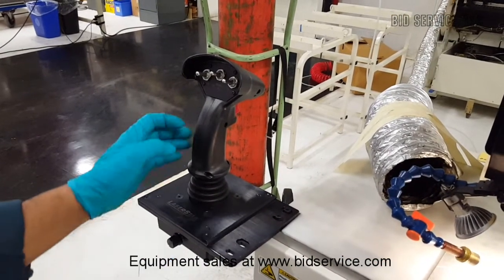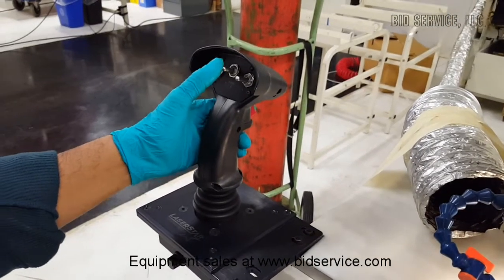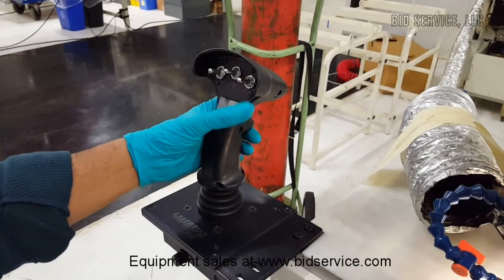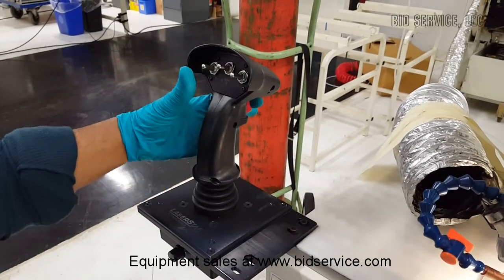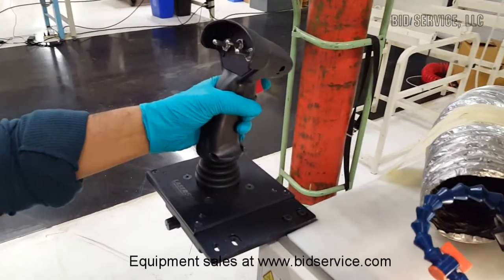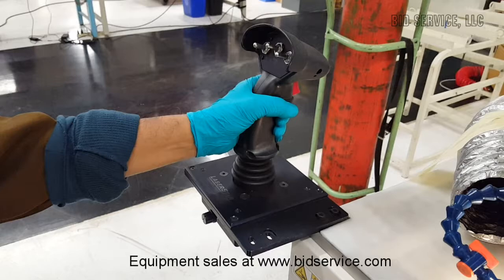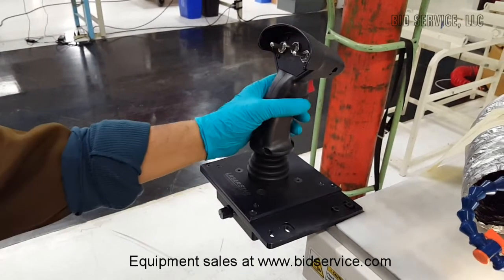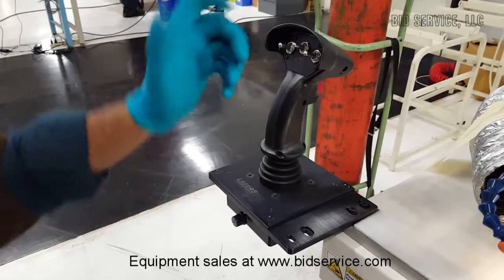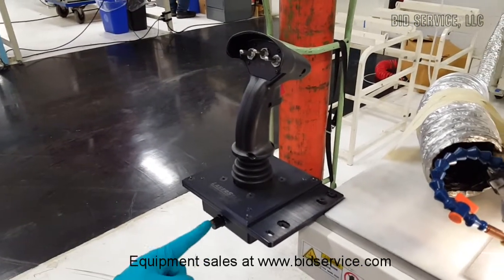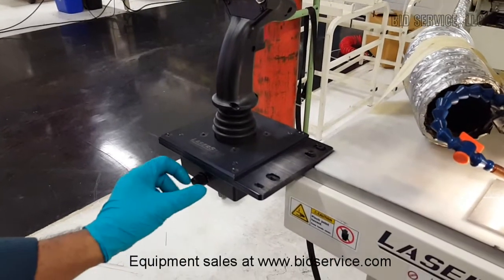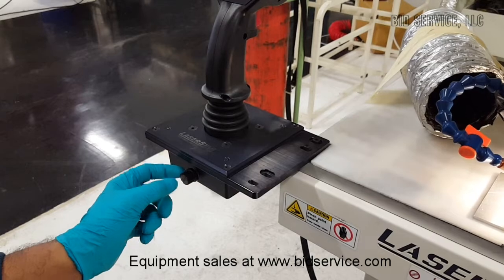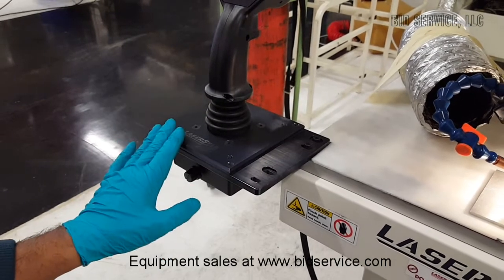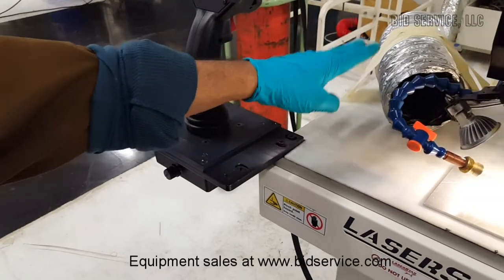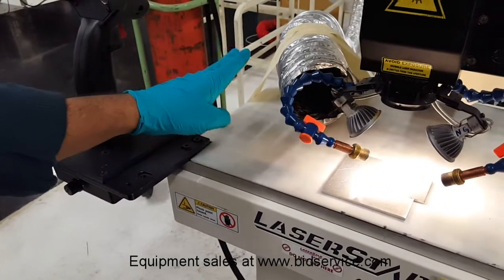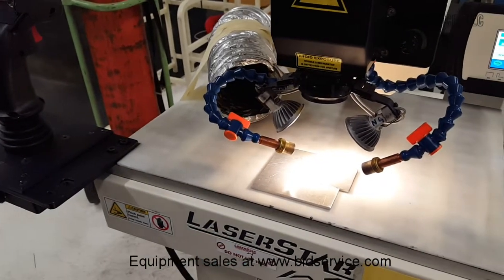It's a multi-axis joystick for moving the table Z up and down, or the rail up and down. And then this is for the Y-axis movement. And also there's a red knob on the back by which we can turn on the laser for a pulse. The joystick can be tilted left to right for X-axis movement, and forward and backward for Y-axis movement. And there's a knob here at the bottom of the stage. All the way counterclockwise is very slow speed, and all the way clockwise is high speed. I have just connected an exhaust here just to eliminate the exhaust fumes coming from this job here.